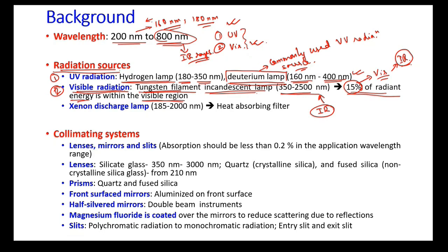IR radiations are associated with heating. They are long-wavelength electromagnetic radiations compared to visible radiations, and care must be taken while using this kind of radiation. There is another visible radiation source — the xenon discharge lamp — which can cover most of the UV-visible radiations from 185 to 2000 nanometers. However, the cost of this lamp is very high.